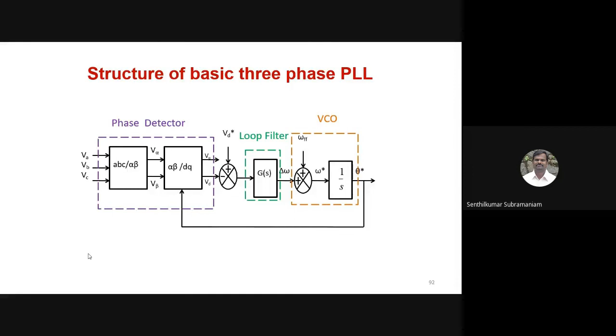The structure of the PLL includes the phase detector, loop filter, and voltage control oscillator. We consider the important indexes affecting PLL performance: unbalance, harmonics, DC offset, and phase jumps.